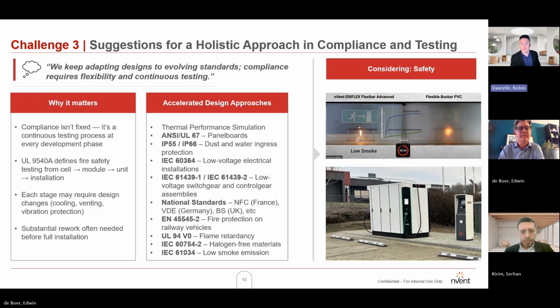Why does this matter? Because safety standards like UL 9540A require rigorous fire testing from cell to module to full installation. Missing these steps can lead, and will lead for sure, to costly redesign and delays before deployment. Thermal simulations, for instance, help engineers identify hotspots and critical thermal pathways in battery modules and racks before they occur in real-world conditions, and potentially add liquid cooling solutions if requested.